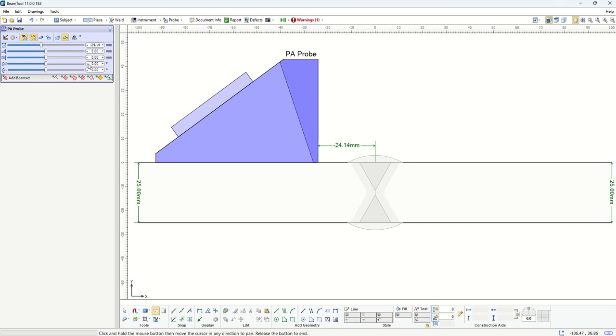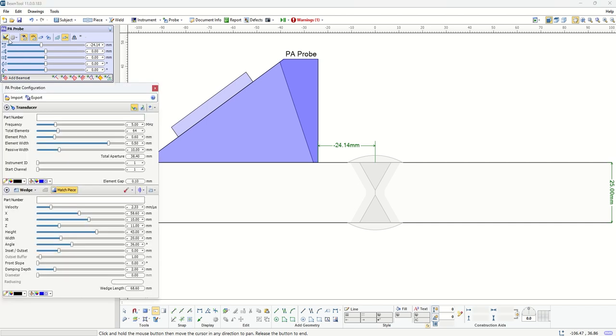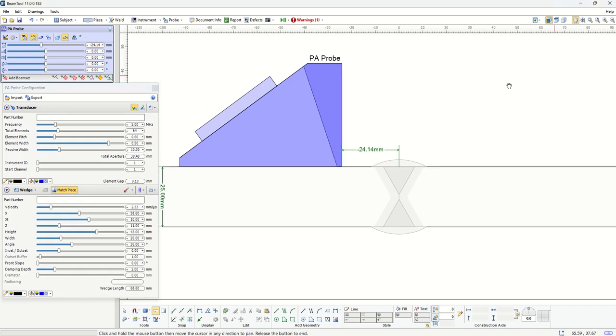When we click on this button here, the view shows details of the wedge and probe. By default, the probe is a 5 MHz, 64-element probe with 0.6 pitch, and the wedge dimensions, including height, angle, and velocity, are all listed here.